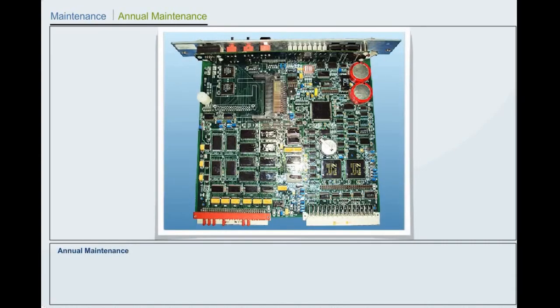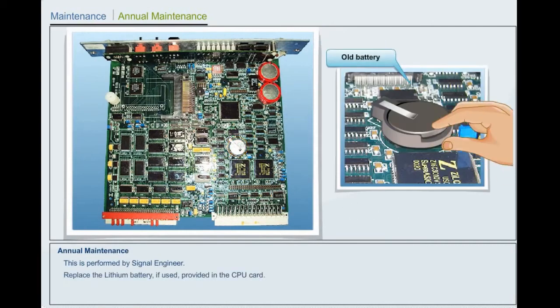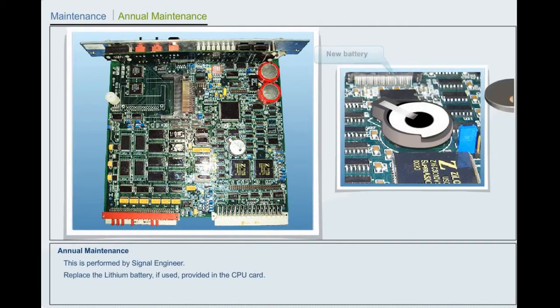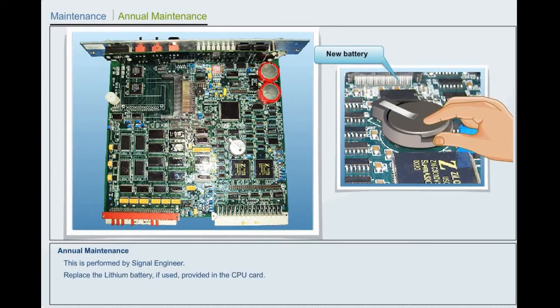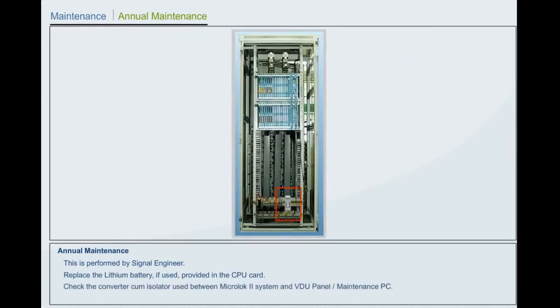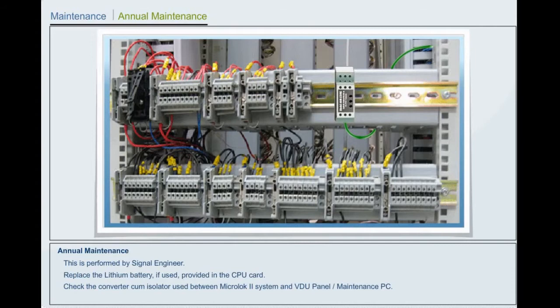Maintenance. Annual maintenance. This is performed by signal engineer. Replace the lithium battery, if used, provided in the central processing unit card. Check the converter cum isolator used between Microlok II system and visual display unit panel or maintenance PC. Perform the inspection activities mentioned in preventive maintenance.